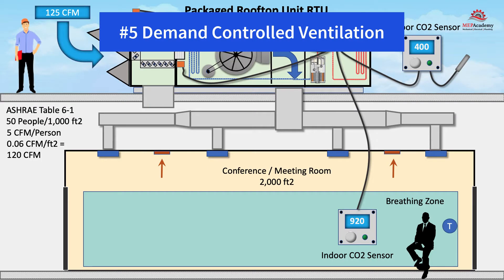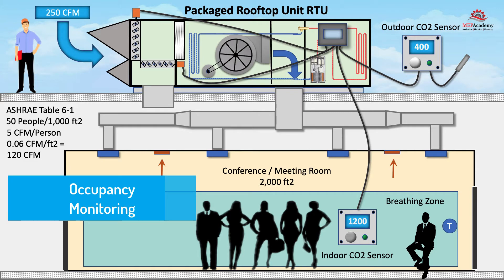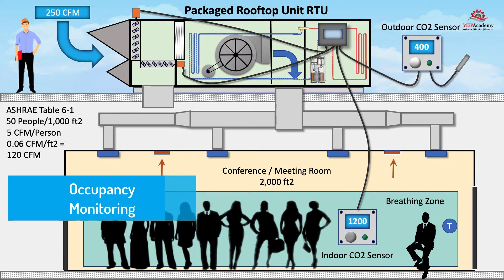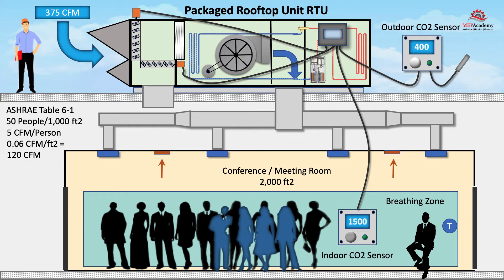Number five: Demand Control Ventilation. It's called demand controlled ventilation because it controls the amount of ventilation based on the demand, which changes with occupancy levels. Some form of occupancy monitoring will be used as the control strategy. Ventilation air is required by ASHRAE Standard 62.1, but providing ventilation air is energy intensive and costly. Providing only what's needed can save on energy and money.